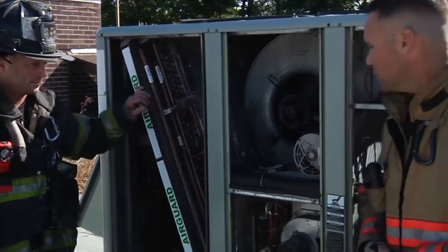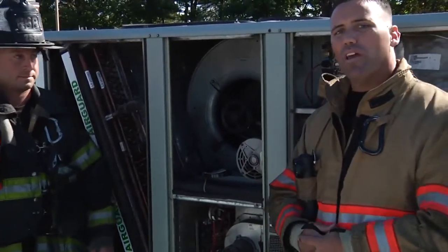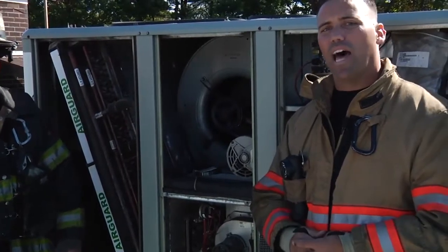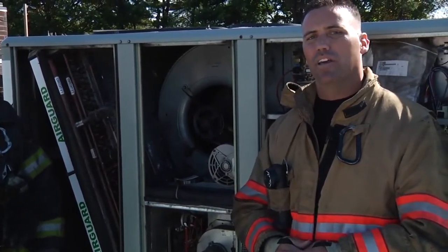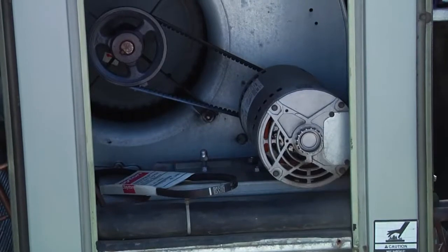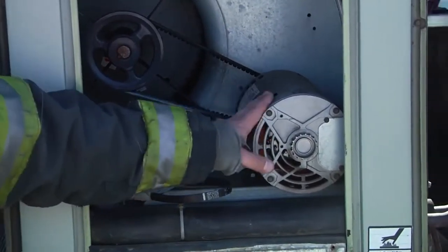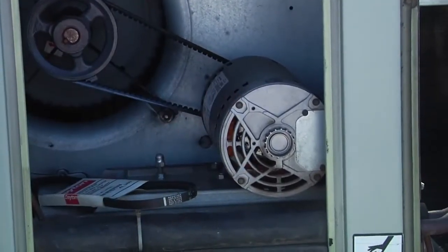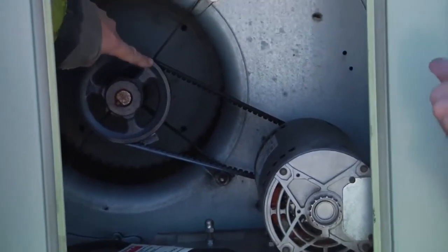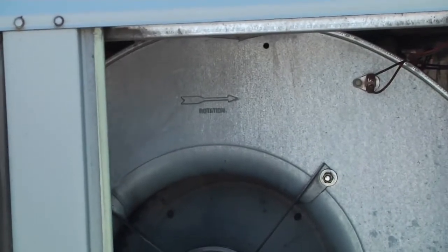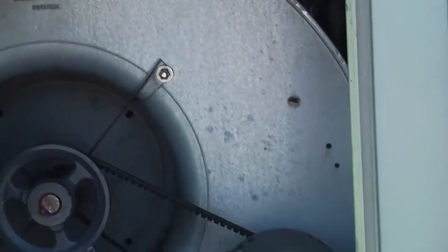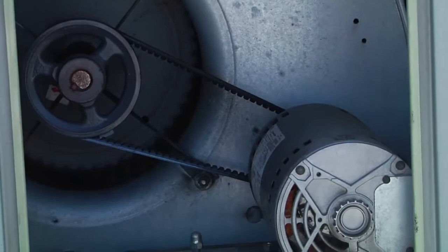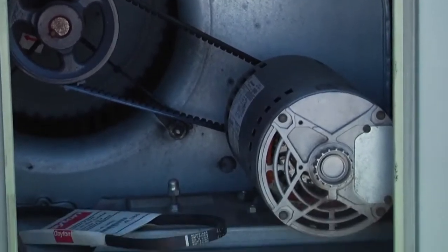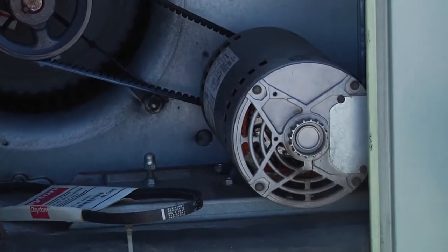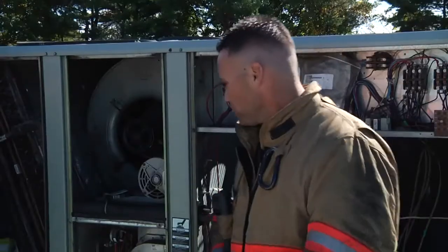Moving down, this will be a big culprit as to why we're getting a lot of our 911 responses involving RTUs. If you look inside, as Anthony will point out, you have the motor, which spins a rubber V-belt, which in turn affects the squirrel cage blower inside. That is the portion that actually moves the conditioned air, whether it be heated air, cooled air, or just cleaner air. That is what's pushing it through the ductwork out into the different compartments in the actual building.